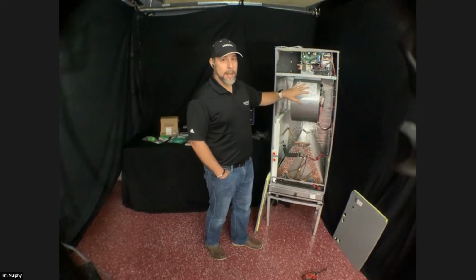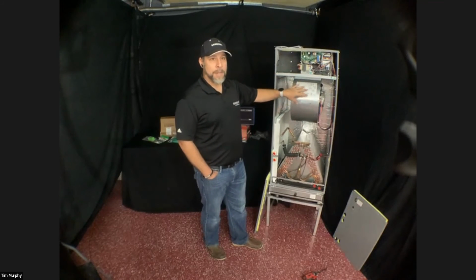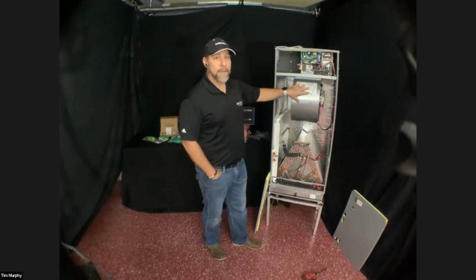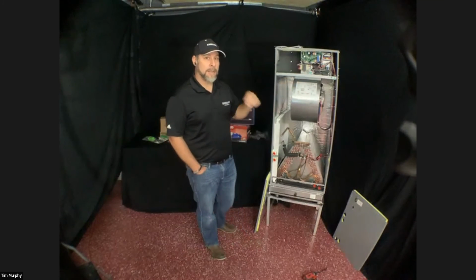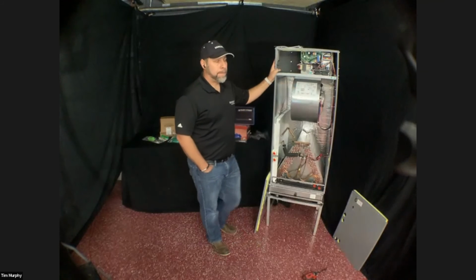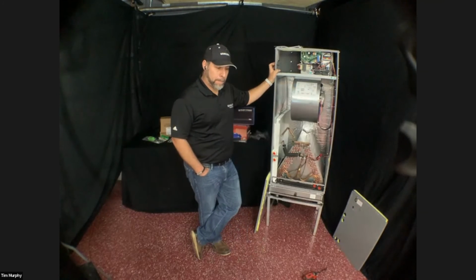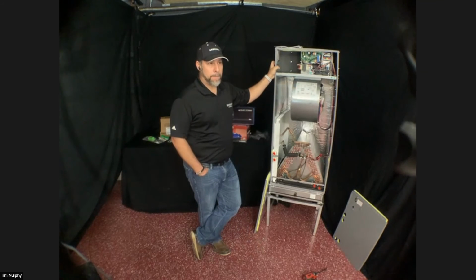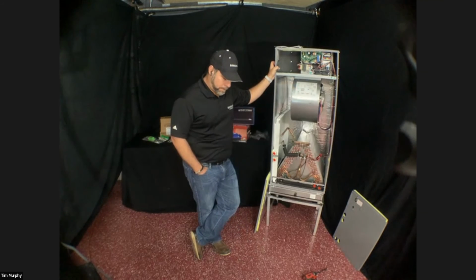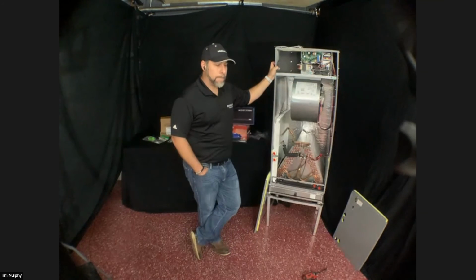The system will heat, like we mentioned before, to 14 degrees for the larger and -4 degrees for the smaller sizes. Tim, I think it's important to note that this is not an auxiliary heat kit. It's not an emergency heat kit. It's a supplemental heat kit. So it's only going to operate when or if the heat pump system couldn't keep up with the heat load in the house, or the cooling load in the house, however you want to look at it.